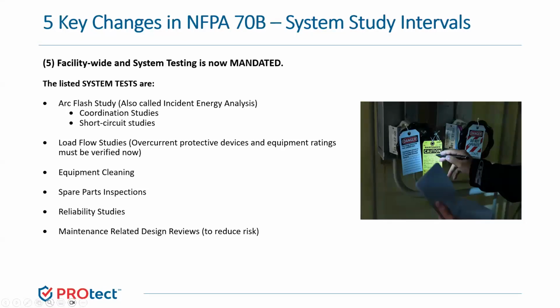Listed system tests include your arc flash studies, also known as incident energy analysis, and these typically include coordination studies and short circuit studies. There's also the addition of the load flow study, covering overcurrent protective devices and equipment ratings that must be verified. There are also requirements for equipment cleaning, spare part inspections, as well as reliability studies and maintenance related design reviews in order to reduce risk.